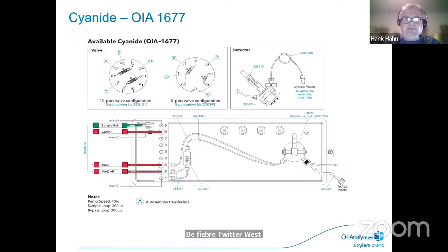And then, as I mentioned, the methods are the recipe. Here below, you'll always see what pump speed we're doing this at, the sample loop size, and that bypass loop size on our flow injection valve. And these are those loops that I have spoken about that go on the valves.